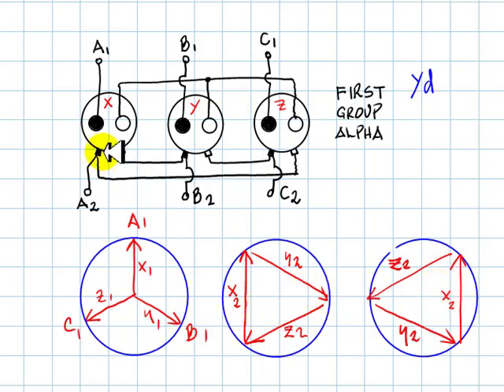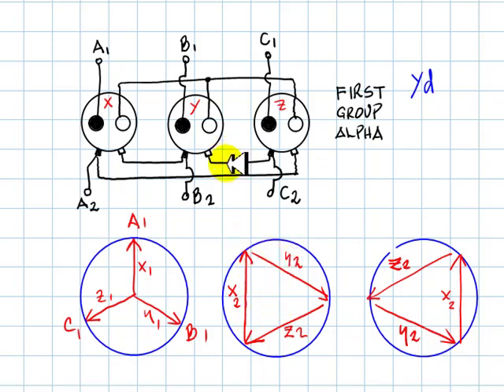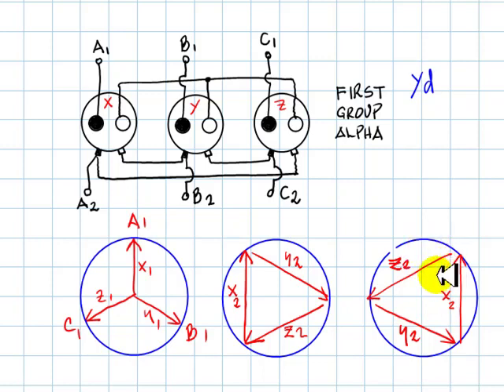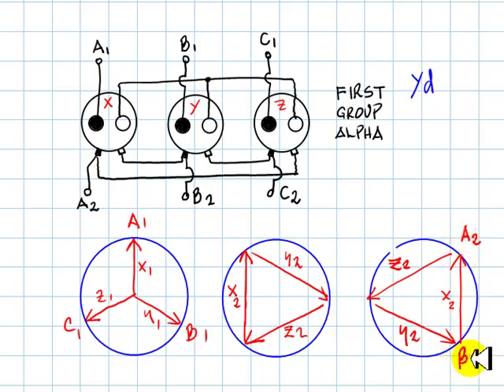Let's see which delta connection we have. The tip of X2 is connected to the tail of Z2 — this is the correct connection. So this is the primary and this is the secondary. Phase A of the secondary is at the tip of X2, and this has to be phase B and phase C of the secondary, and they comply.